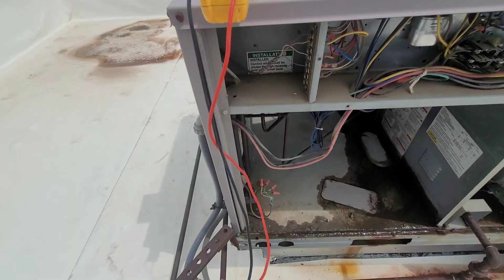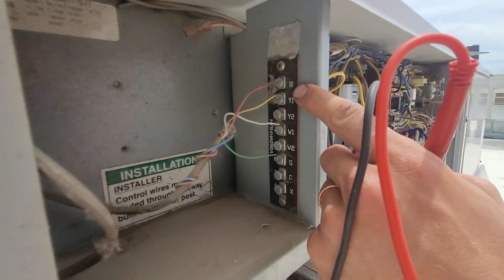Right from R to C on the thermostat terminals, because how it's supposed to work is this transformer sends 24 volts down to the thermostat through this wire here, and then it sends it back up on whichever wire it wants. So if it sends it up on the G, it'll run the fan. If it sends it up on the W, it'll run the heat. If it sends it up on the Y, it'll run the air conditioning. And the R is just the control voltage going downstairs. So if we check from C to R, we should get nothing, which we do.